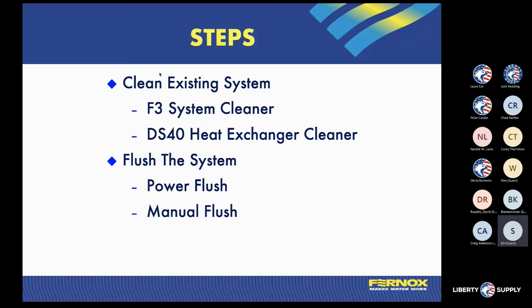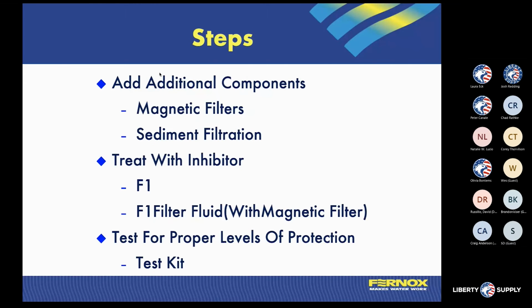So you can flush the system doing a power flush, which we'll talk about machines and tools that we have for doing power flush, which is a machine style flush. And then we also have the ability to do a manual flush as well with a mechanical flush. And then we can do additional components, and we've talked about magnetic filters and sediment filtration. And then the final step is obviously putting that inhibitor to balance the water or balance the fluid that we have in our system and keep that at proper levels via doing testing and maintenance on the levels of inhibitor that have been put into the system. Obviously, during the year, you don't know if something has been changed and we added fresh water. We always have to make sure that our inhibitor levels are correct. So that's going to be something you're going to do as part of your maintenance plan throughout the season.